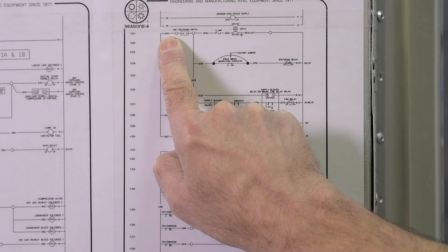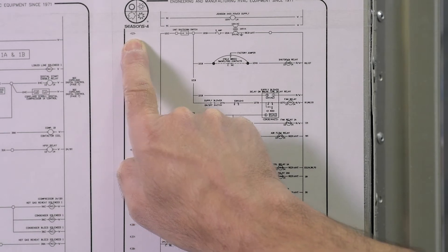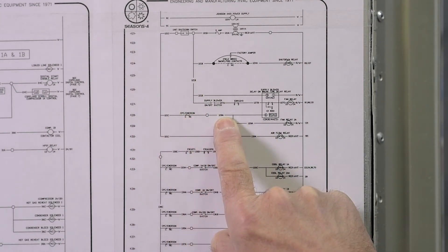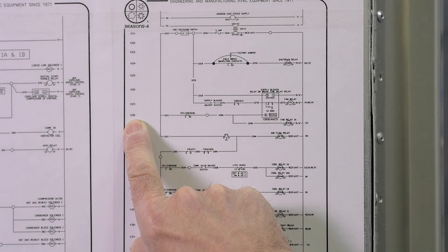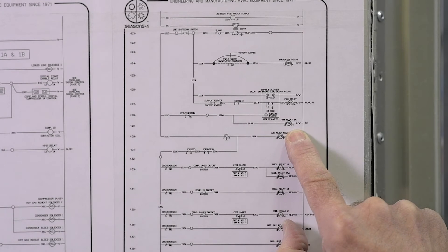The 121 wire number indicates what line number it starts on. That 121C comes down and goes through a controller and becomes 128A. That 128A references the line number 128 where that wire started, comes down and comes into a relay.